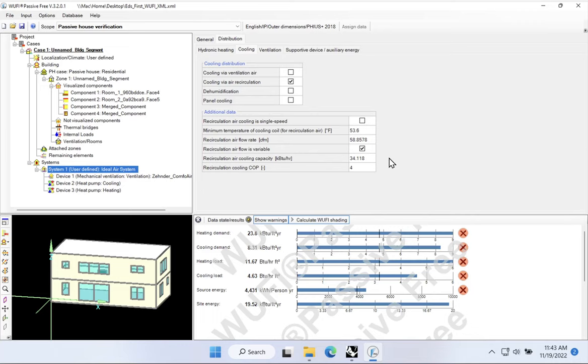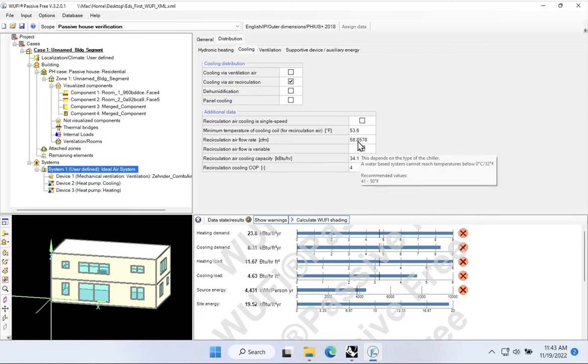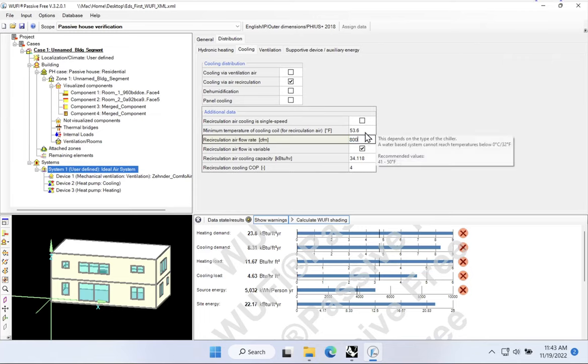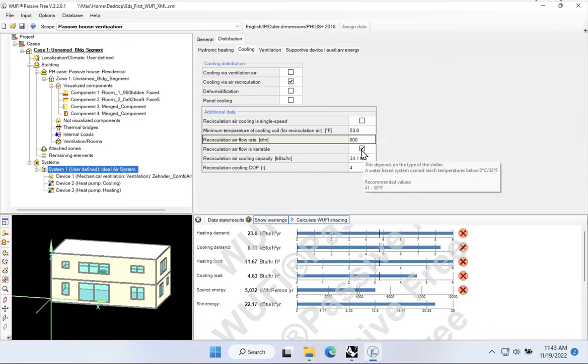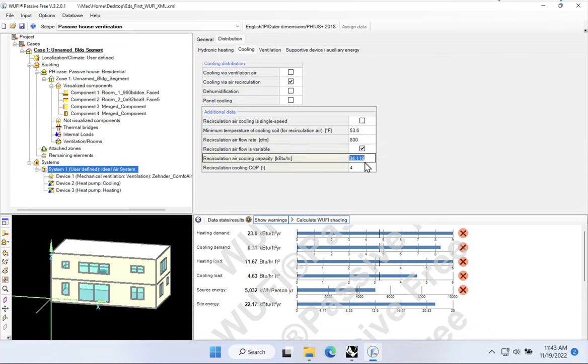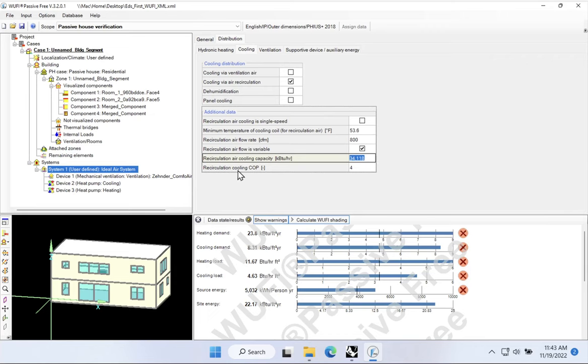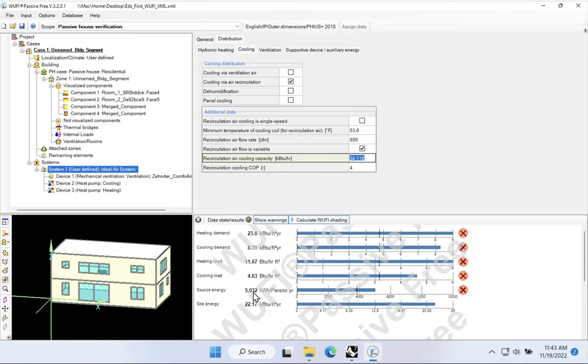Here is where you can come in and input things like the total CFM of the cooling system. I don't know, it's probably for a building like this, 800 to 1,000 CFM, something like that. Is it variable flow? What's the total size here? What's that, three tons? 34,000 BTUs, somewhere in that range. And then what's the COP? So here's where we would model out the equipment for the cooling side of our heat pump system here. And notice down here that my source energy is now quite a bit different than it was when we started. Obviously, we have the equipment now which is providing heating, providing cooling, working at some level of efficiency. So WUFI is able to more accurately calculate the source energy here.